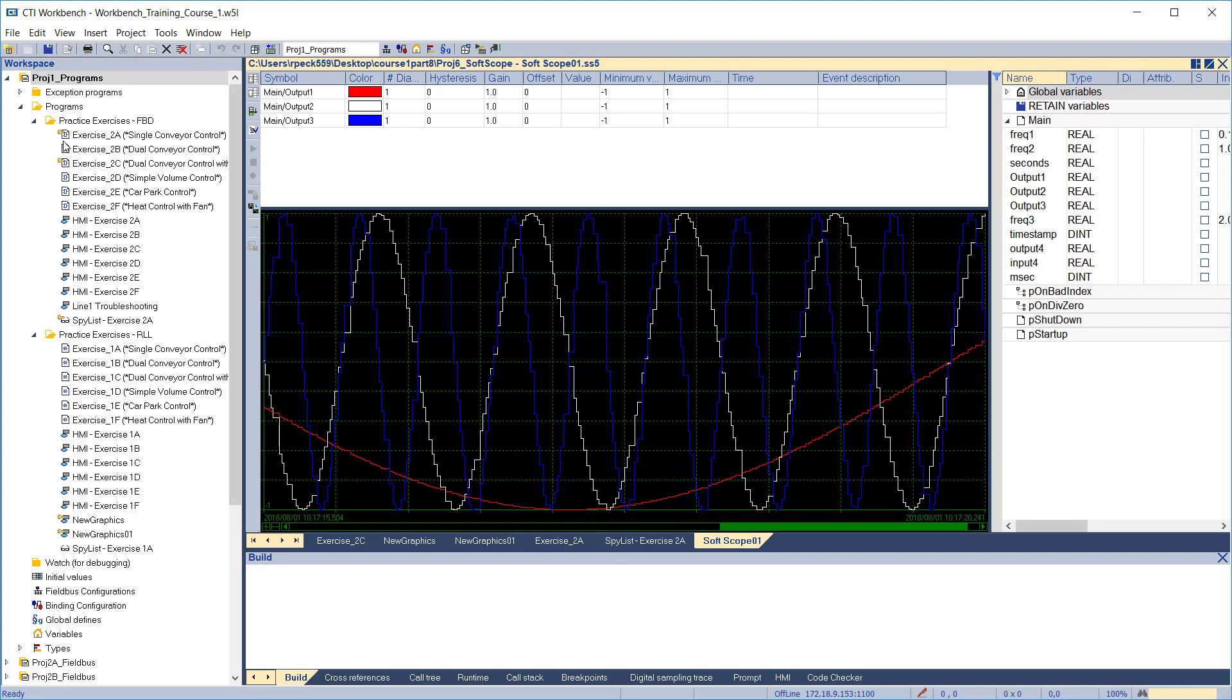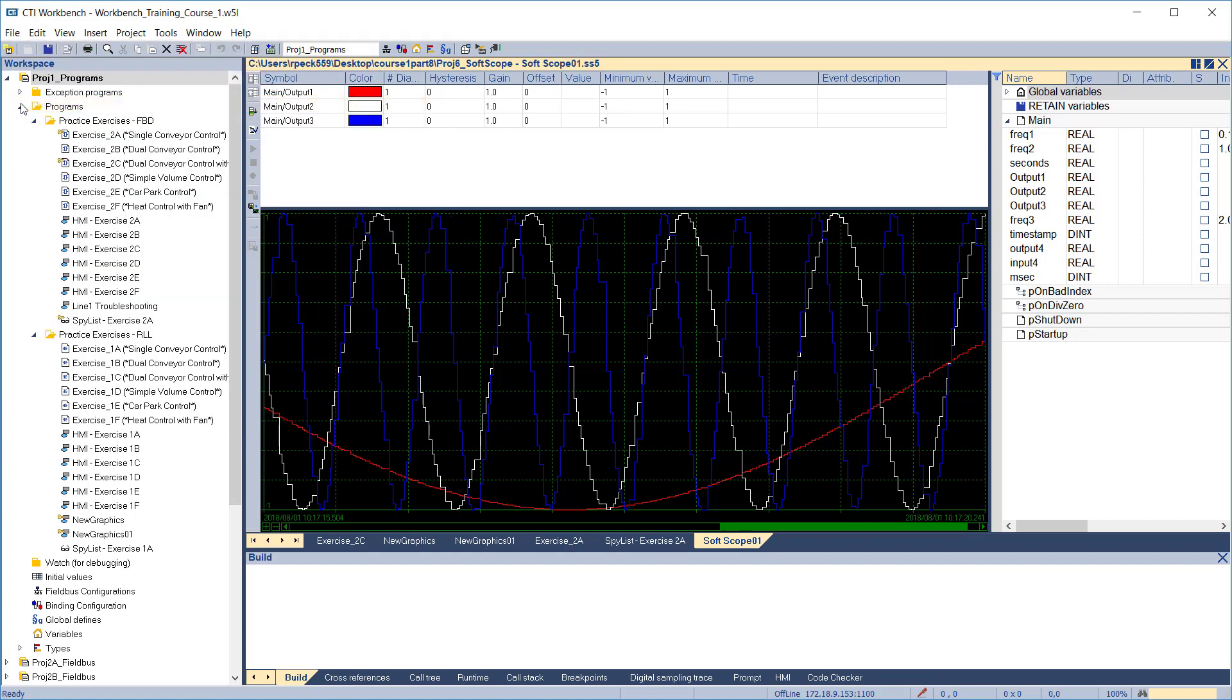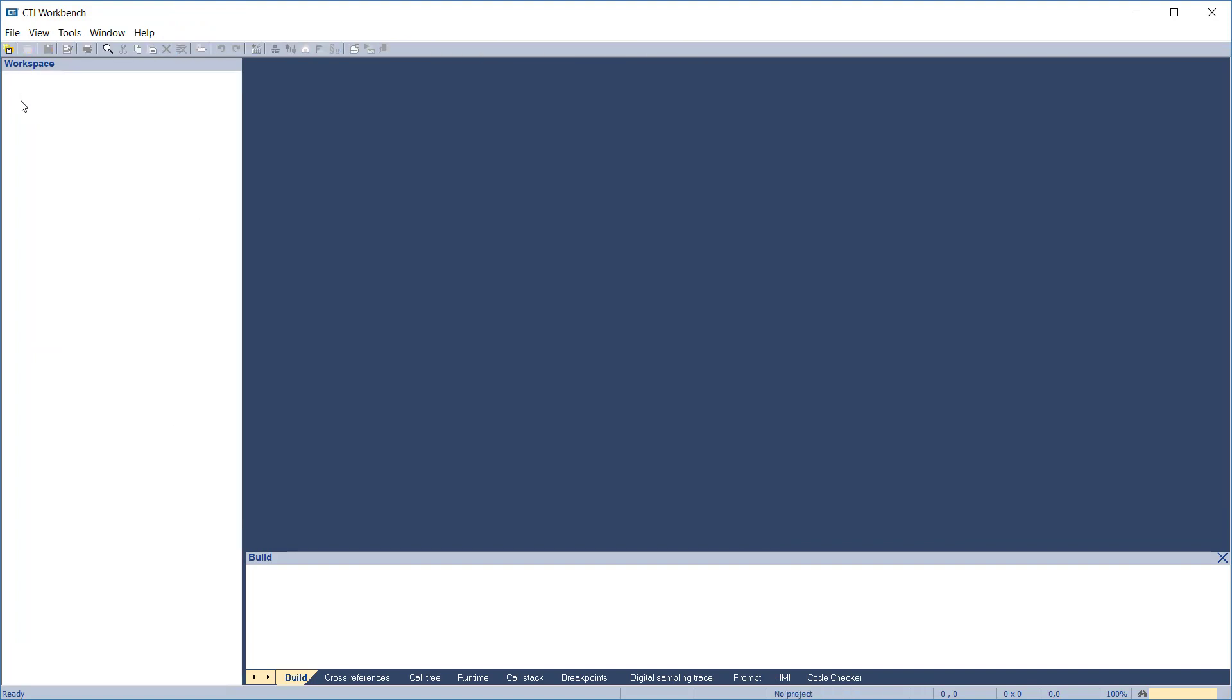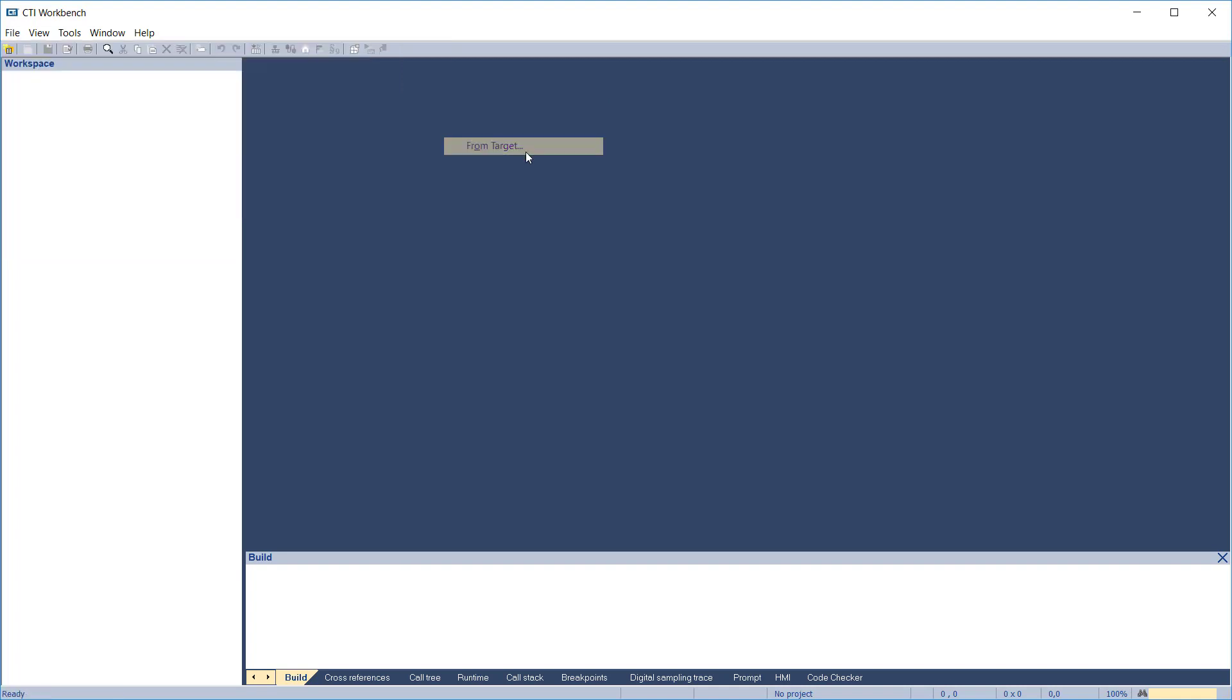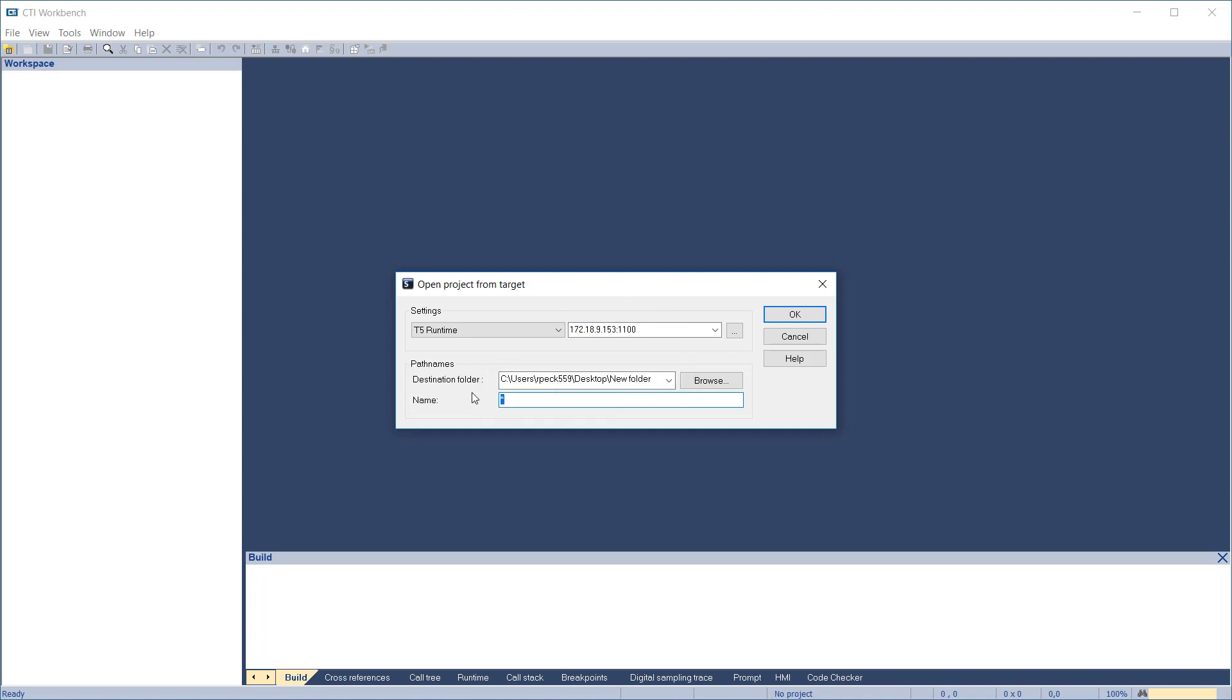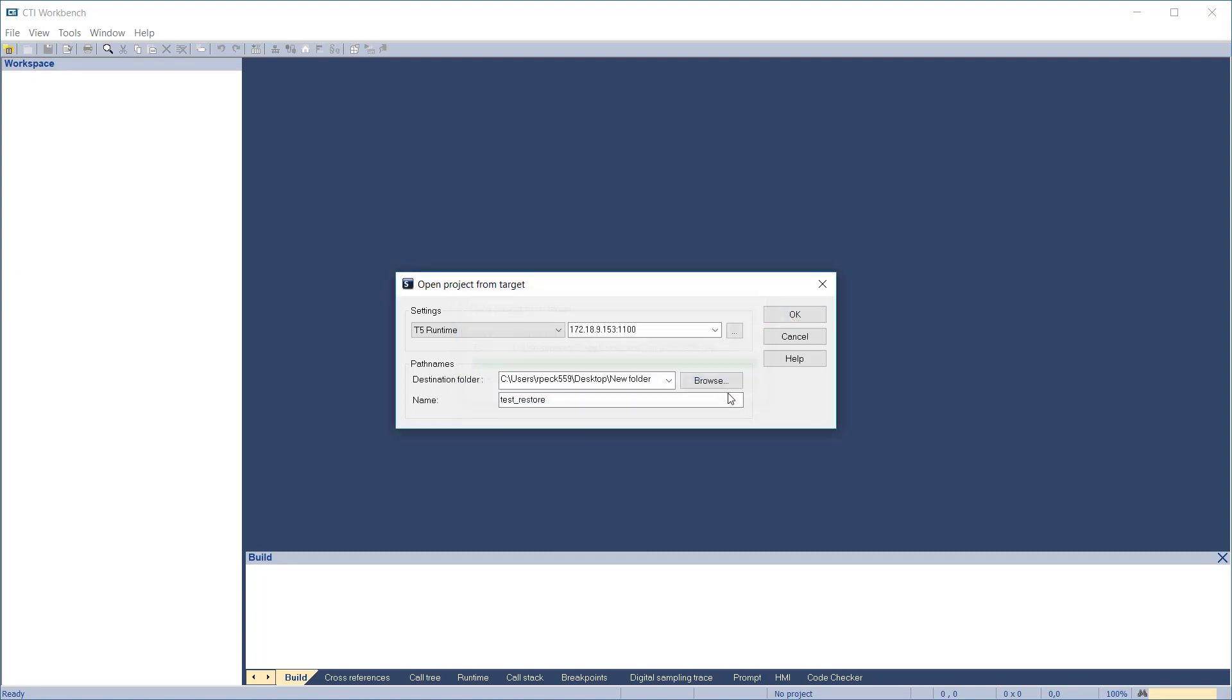If you have saved the project source files to the target, it's easy to recover them. Close any open workspace. Then click file, add existing project from target. The open project dialog box comes up to allow you to enter the IP address of the target, the disk folder for storing the project after it's downloaded, and a new name for the project. We'll call it test restore. Click OK to proceed. The project is downloaded from the target and the workspace opens ready for editing.